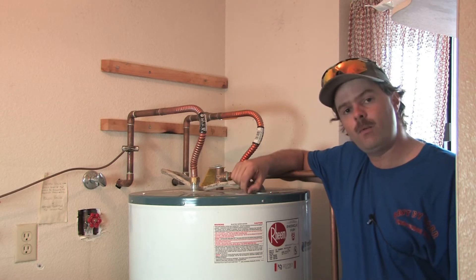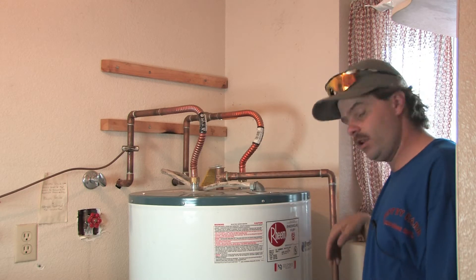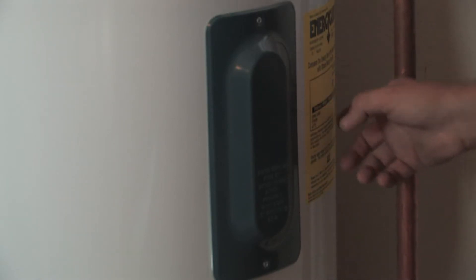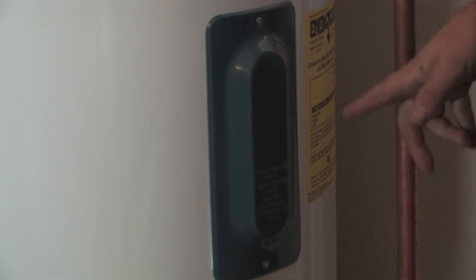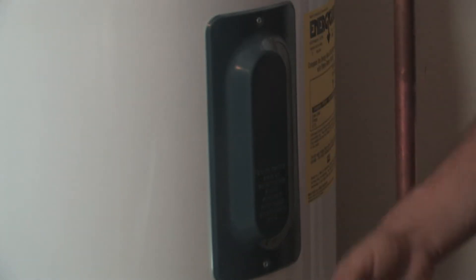The first hour rating is on every single water heater. You'll always see a yellow tag called an Energy Guide. The Energy Guide has information on how many therms or kilowatts it will use and the average annual cost. It also has a number showing capacity and first hour rating — that's what you design your water heater selection to.